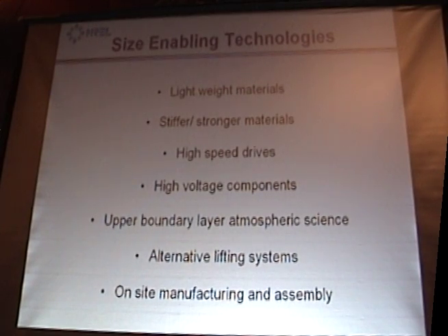High-speed drives. And I want to add to that lightweight drives, because we're looking at superconducting generators right now. Twenty years ago they were kind of science fiction, but they've actually built some motors that work in ships at 36 megawatts. So full scale, that's kind of the size we want to get into. They're a third the weight of a classic direct drive generator.